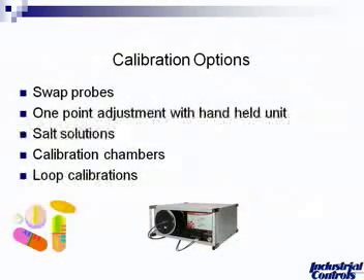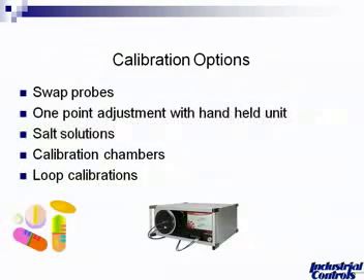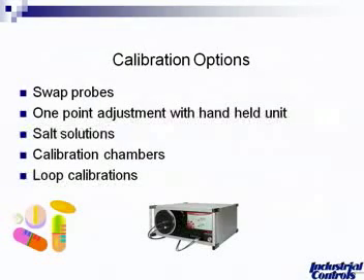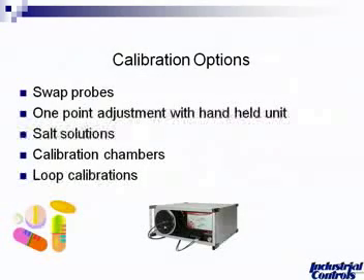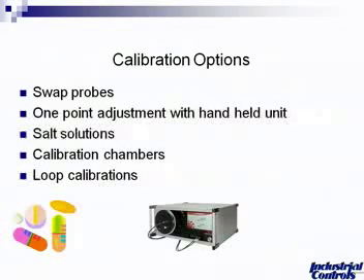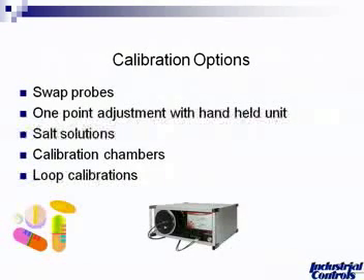So how do you calibrate in the field? A very easy way would be to have a calibrated probe swap — take a probe from your stock that's been freshly calibrated, pop the old one off your transmitter, put the new one on, and there's no further adjustment necessary. You can also do, on rare occasions, a one-point adjustment with handheld units. That's not a true calibration, but it gives you a little better accuracy at your critical points.